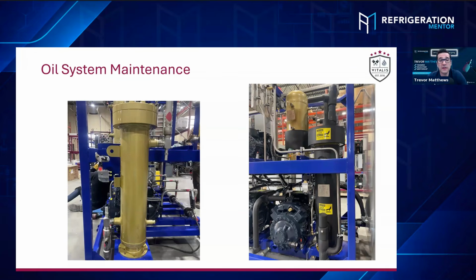Yeah, that's a great tip. And just always remember, there's still going to be pressure inside there after you isolate it. So you don't just rip out all the bolts and knock it off. You always leave 2 or 4 bolts in there, just cracked, so you can knock it and release any pressure. Don't blow oil in your face. So safety, always safety first. And what I also like to see all the time is if you relieve the pressure out of this little service port through a gauge manifold.